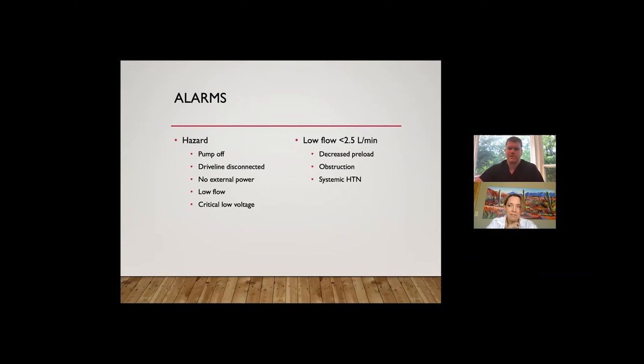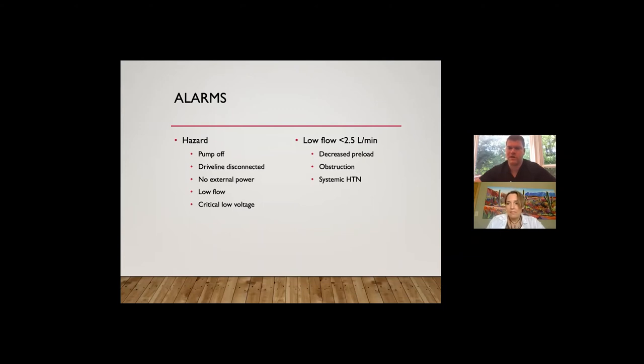The major hazard alarms to be aware of include pump off, driveline disconnected, no external power, low flow, and critical low voltage. Low flow is a common alarm that you have to put into clinical context — figuring out why the pump is not providing the cardiac output that is its goal. Things that can decrease flow through the pump include decreased preload, obstruction of the pump, or systemic hypertension.